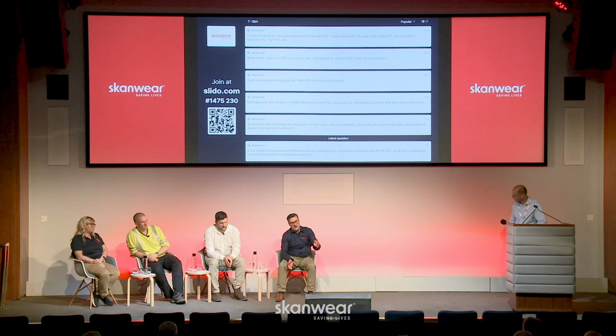So to go back, ELIM is a bit of a myth. It was brought in to kind of match up with the pass or fail situation with the closed box arc test. Class 1, Class 2, pass or fail, no grey area, no in between. A cal rating gives you a defined protection level for the clothing you're wearing. So ELIM, if I had my way, I'd remove that rule and just keep it like the USA keep it, ATPV or EBT. Okay. Hope that helps.